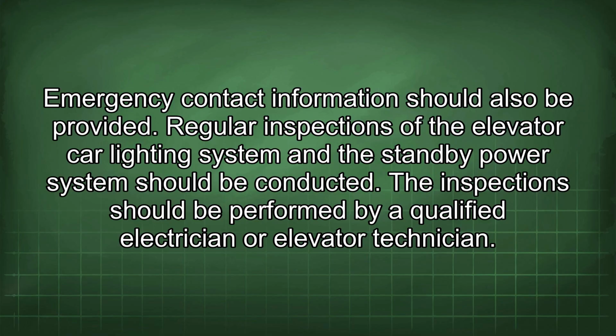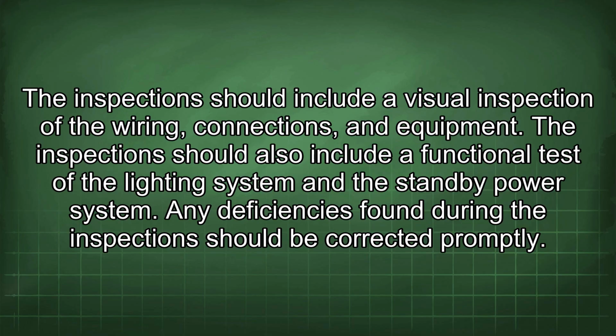Regular inspections of the elevator car lighting system and the standby power system should be conducted. The inspection should be performed by a qualified electrician or elevator technician. The inspection should include a visual inspection of the wiring, connections, and equipment. The inspection should also include a functional test of the lighting system and the standby power system. Any deficiencies found during the inspection should be corrected promptly.